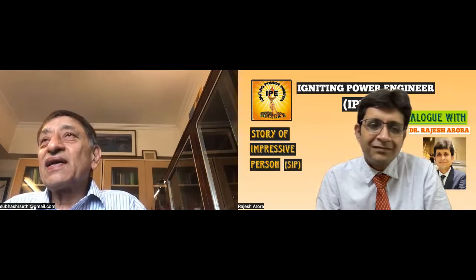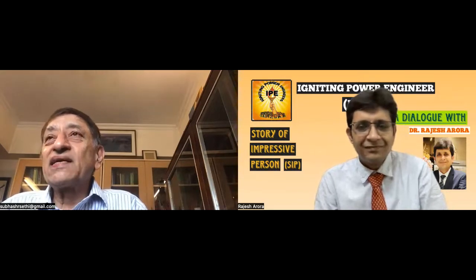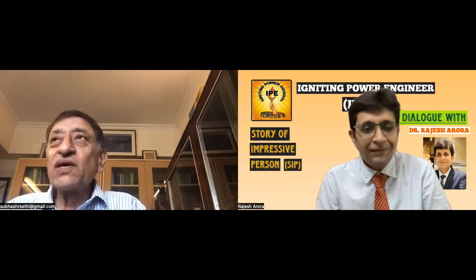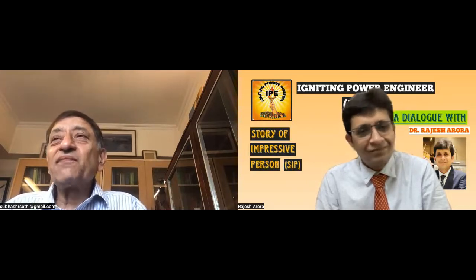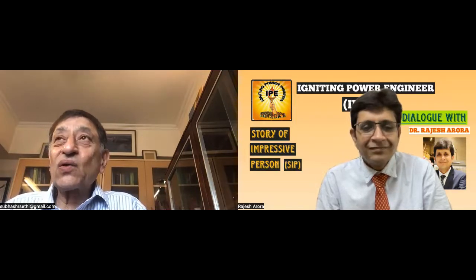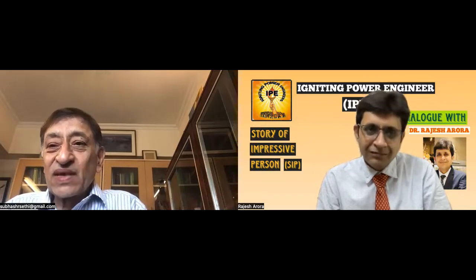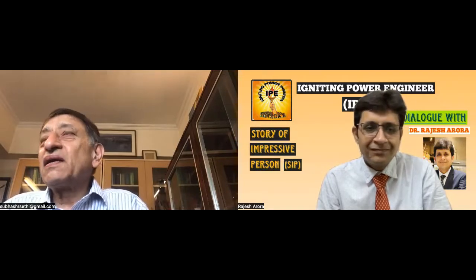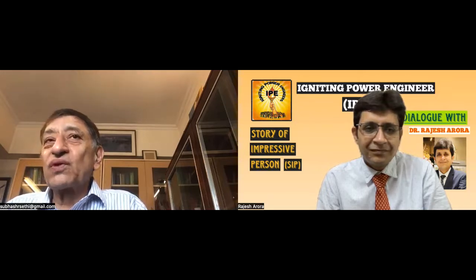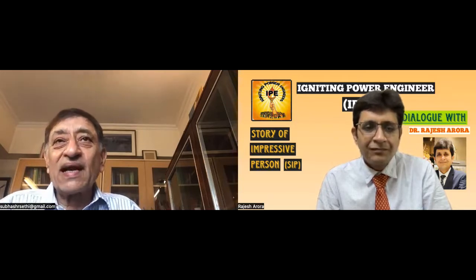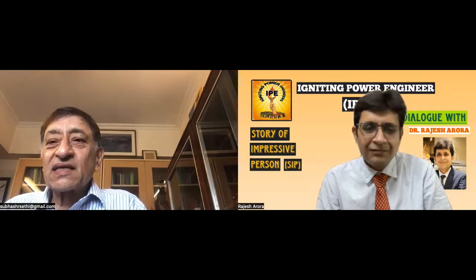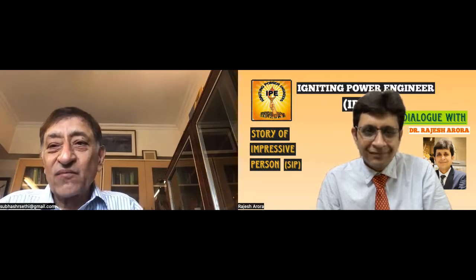The gas turbine had the unique facility that it was one push-button start. You just give a start command and it will go up to synchronizing, and you can synchronize either automatically or manually as the case may be. The loading took about 15 minutes to go to full speed, and you can synchronize with the grid and start supplying power of 30 megawatt.